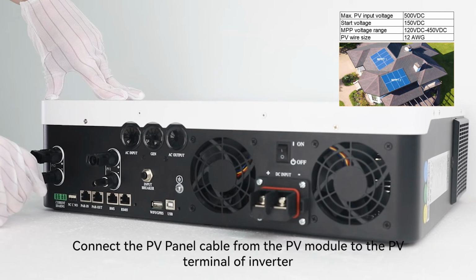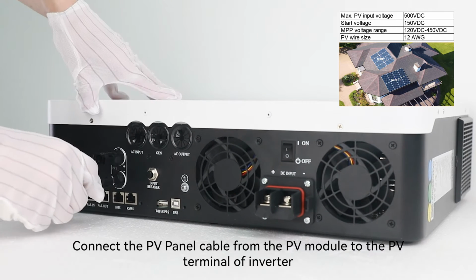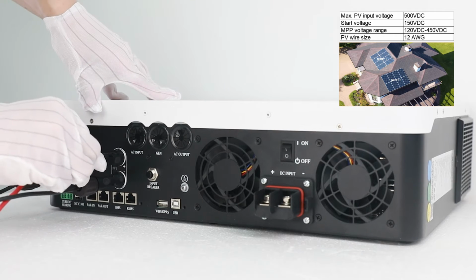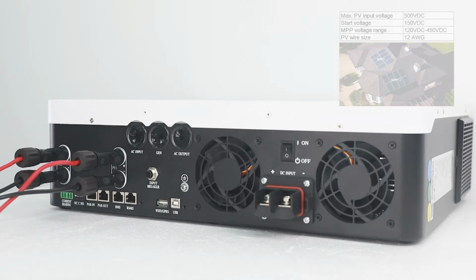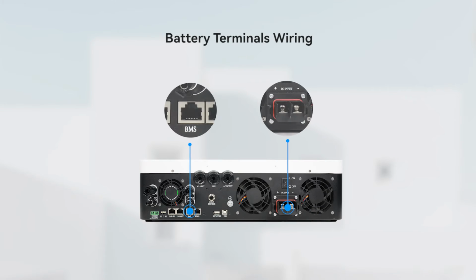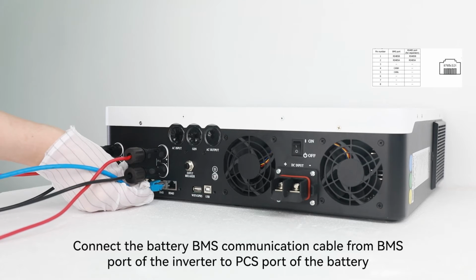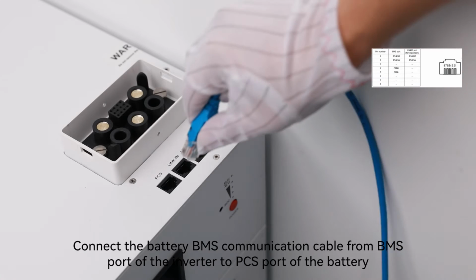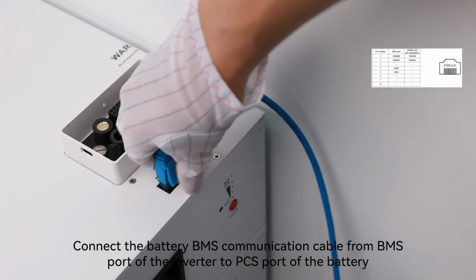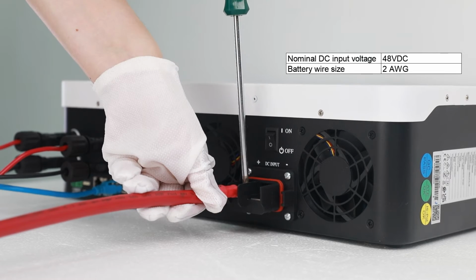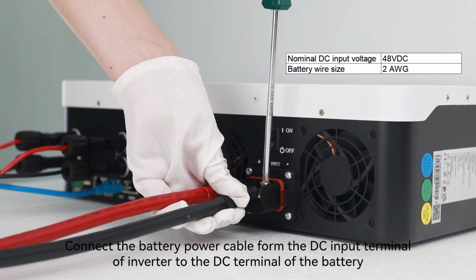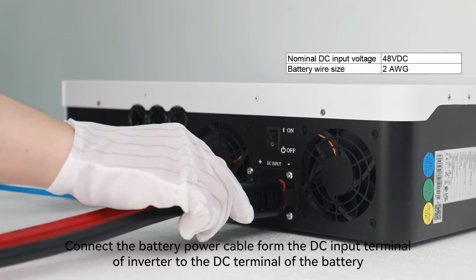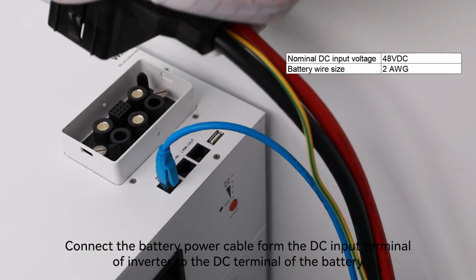Connect the PV panel cable from the PV module to the PV terminal of the inverter. Battery terminals wiring. Connect the battery BMS communication cable from the BMS port of the inverter to the PCS port of the battery. Connect the battery power cable from the DC input terminal of the inverter to the DC terminal of the battery.